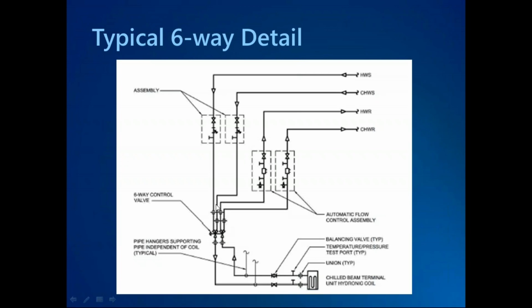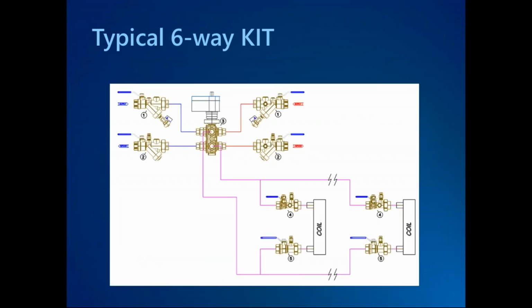But if we go back to the 6-way and look at the return leg coming back to your chilled and hot water respectively, you have some sort of balancing valve, some sort of isolation valve, and they're showing an additional air vent here. So the components required are pretty typical. And if we look at what that looks like in more of a sketch type view as opposed to a line drawing, we have supply strainers coming into the valve, automatic balancing valves on the return, and then piping in your dual temp zone. Again, we'll touch back on this a little bit later on.